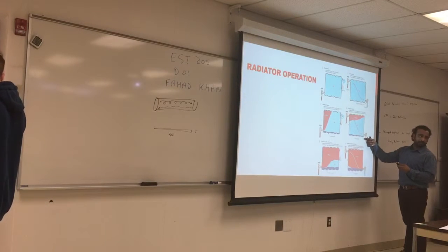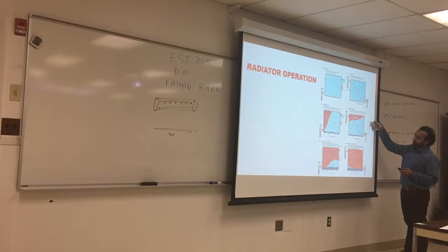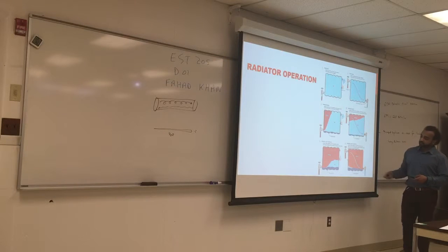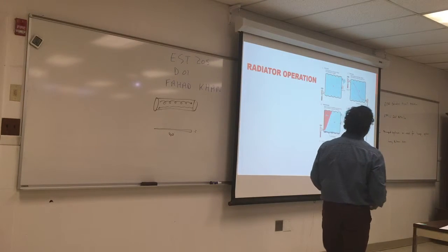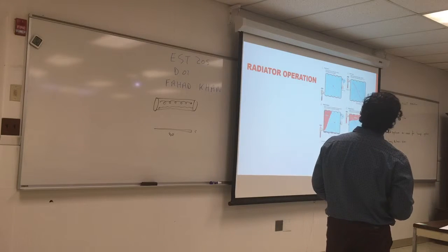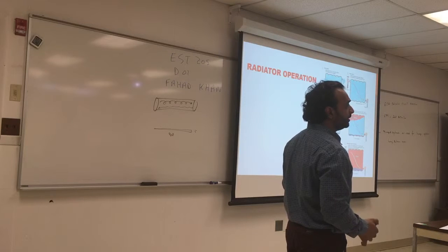It's operated by the weight of the steam, and you want to maintain the steam in the pipe, and the vent will vent all the air out, with the same function. The two pipe system is more efficient in the sense that it will let all the air out, and you'll have more steam in the radiator. So, probably if you work in heating, you will run through some of those steam systems.